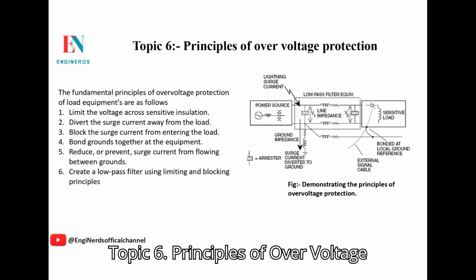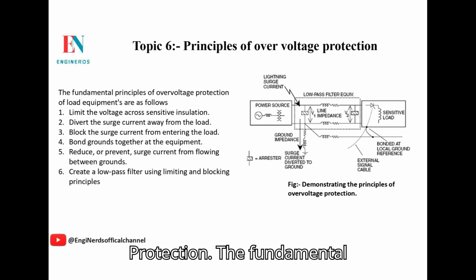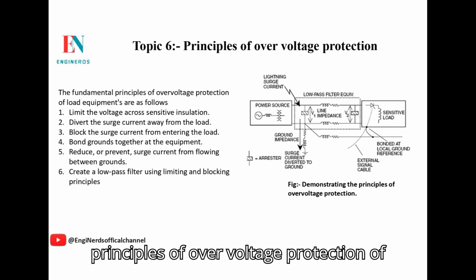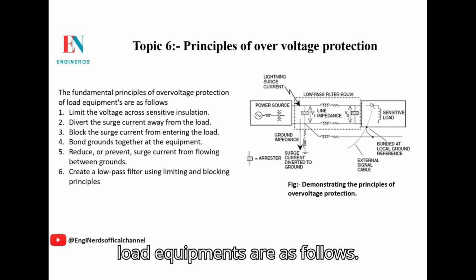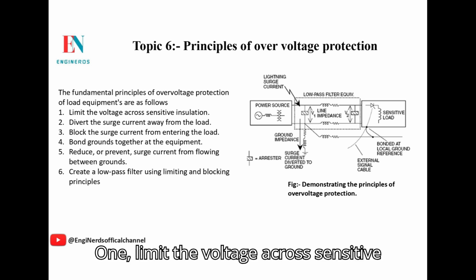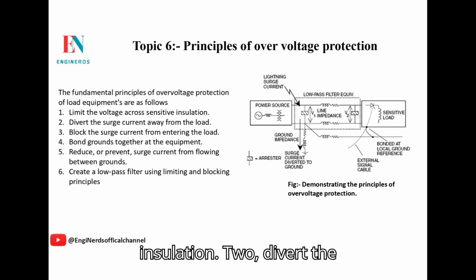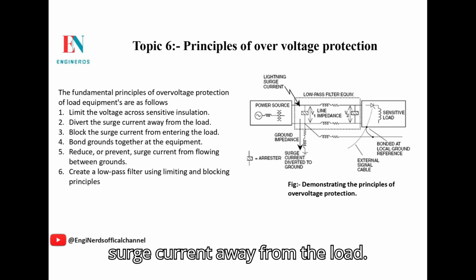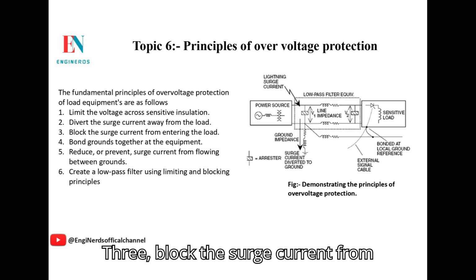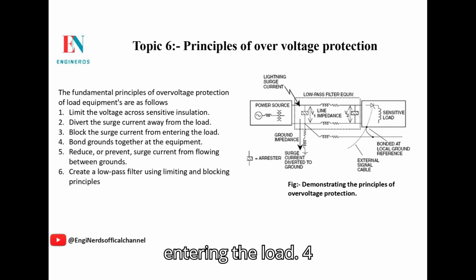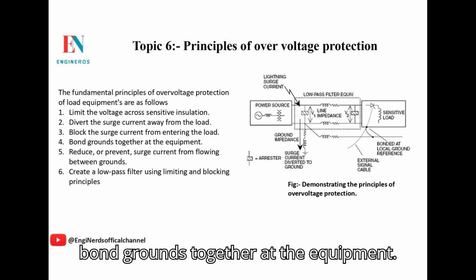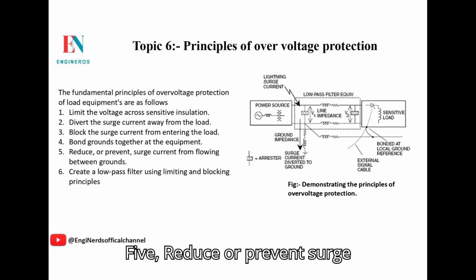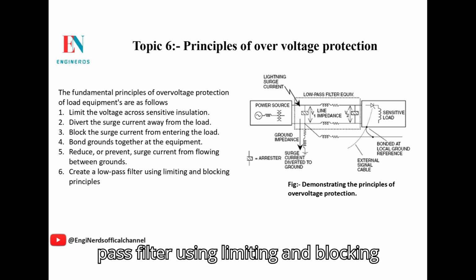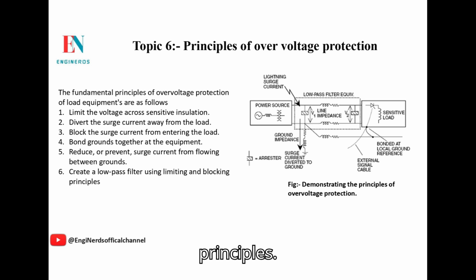Topic 6: Principles of overvoltage protection. The fundamental principles of overvoltage protection of load equipment are as follows. 1. Limit the voltage across sensitive insulation. 2. Divert the surge current away from the load. 3. Block the surge current from entering the load. 4. Bond grounds together at the equipment. 5. Reduce or prevent surge current from flowing between grounds. 6. Create a low-pass filter using limiting and blocking principles.